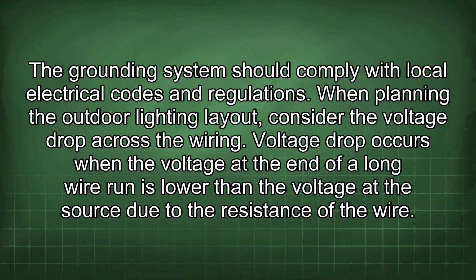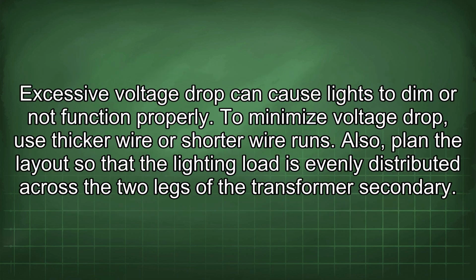When planning the outdoor lighting layout, consider the voltage drop across the wiring. Voltage drop occurs when the voltage at the end of a long wire run is lower than the voltage at the source due to the resistance of the wire. Excessive voltage drop can cause lights to dim or not function properly. To minimize voltage drop, use thicker wire or shorter wire runs. Also, plan the layout so that the lighting load is evenly distributed across the 2 legs of the transformer secondary.